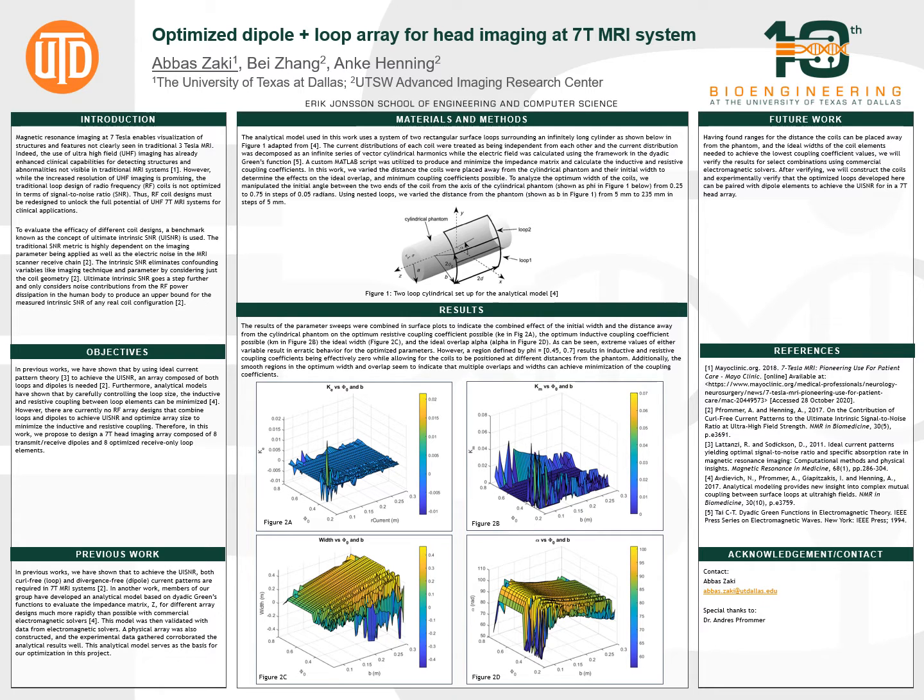And so using the optimization toolbox in MATLAB and a script that essentially uses the dyadic Green's functions outlined more in depth in other works of literature, we find the electric coupling as well as the magnetic coupling coefficients and plot them for a parameter sweep in both the distance that the coils are placed from the phantom as well as their initial width for those coil elements.